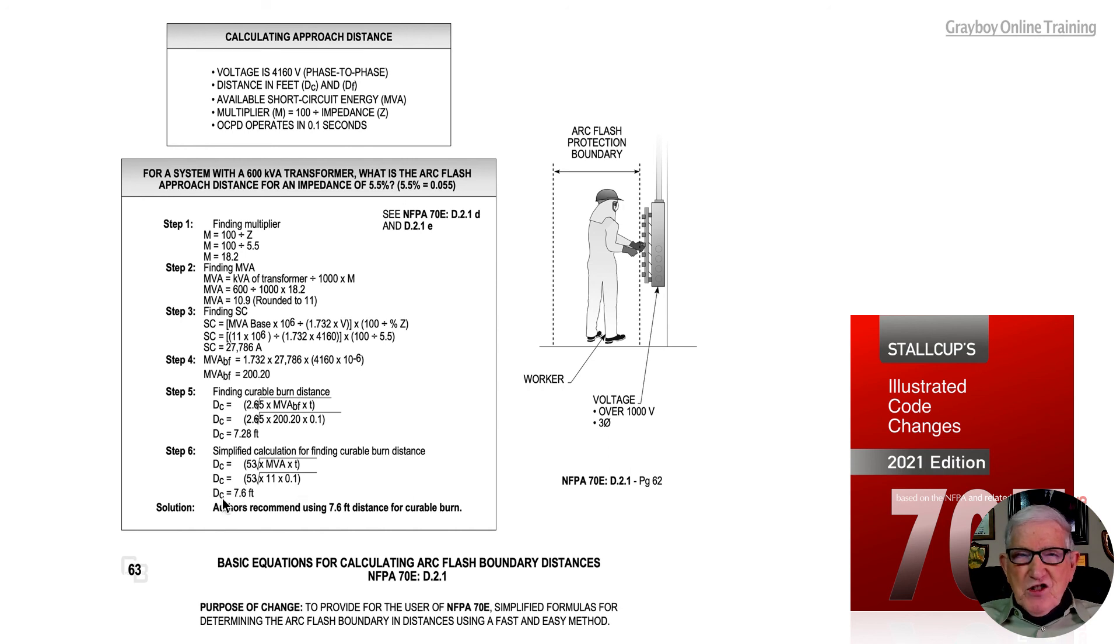This gives us Dc of 7.6 feet. If we took a bolted fault as in step five, after doing the more complicated math it would be 7.28. So 7.6 gives a good estimate of the distance for a curable burn, which would be no more than a second degree burn.